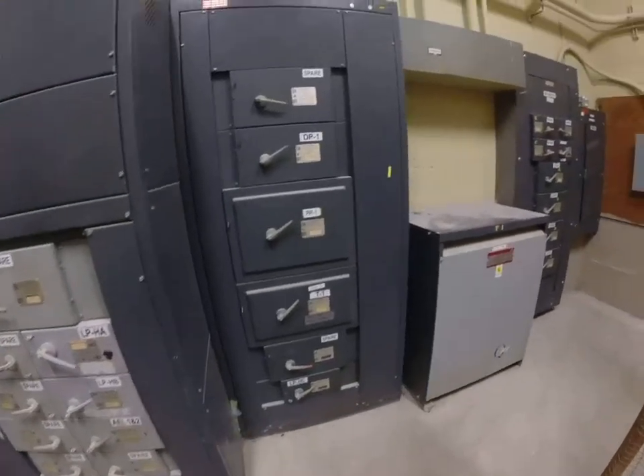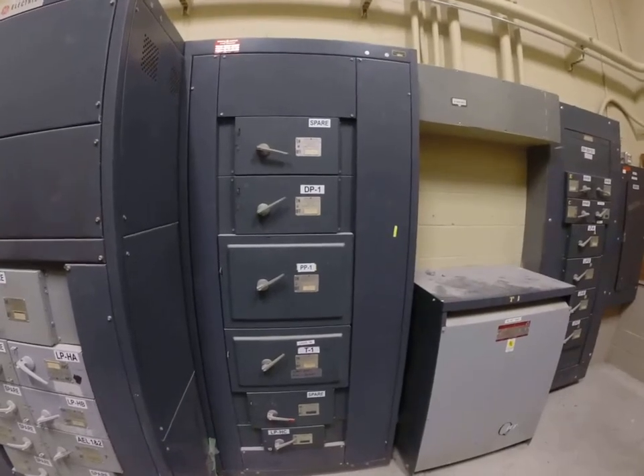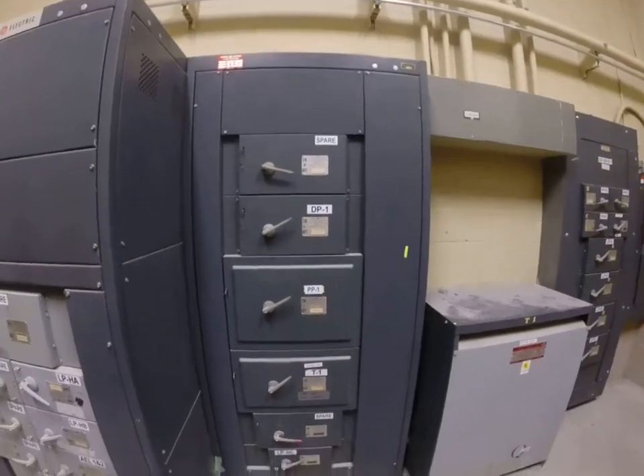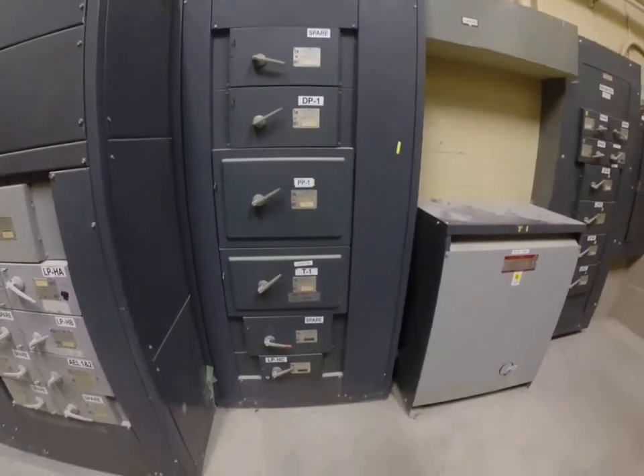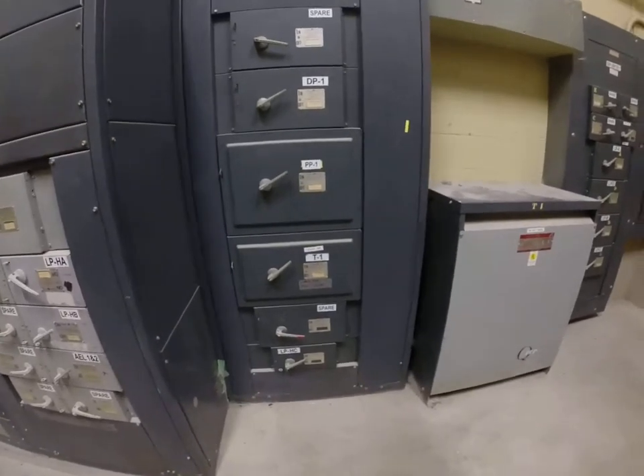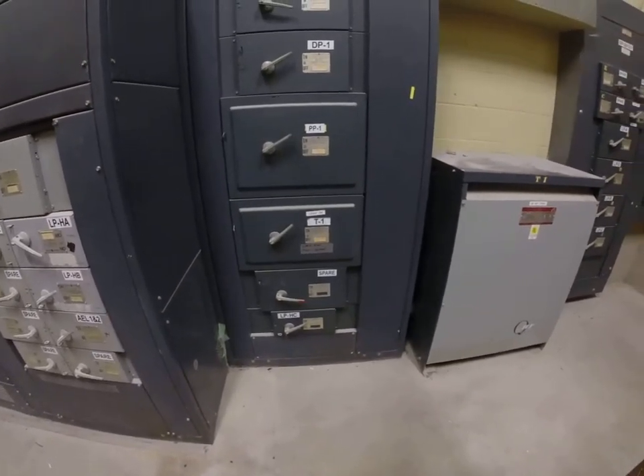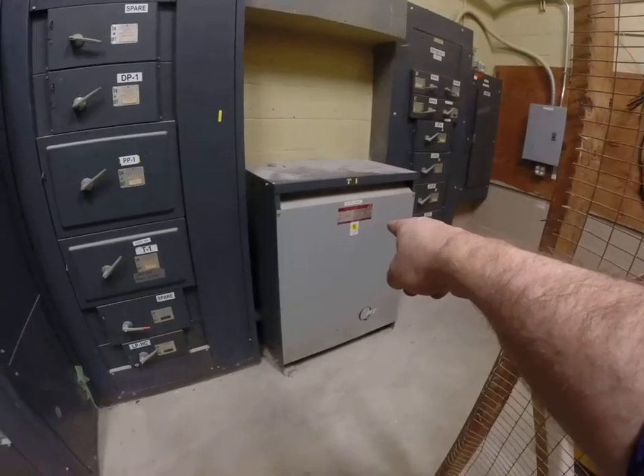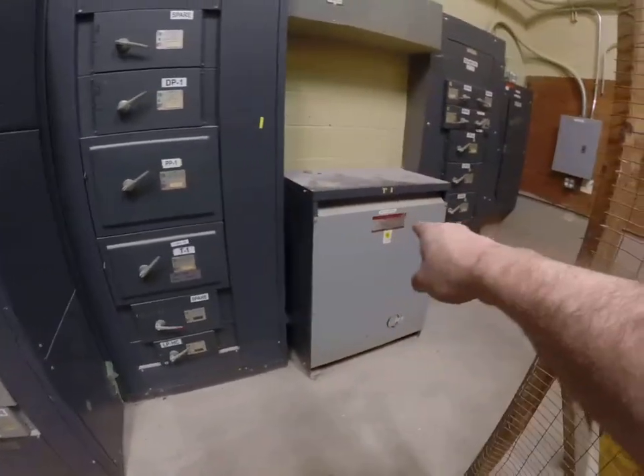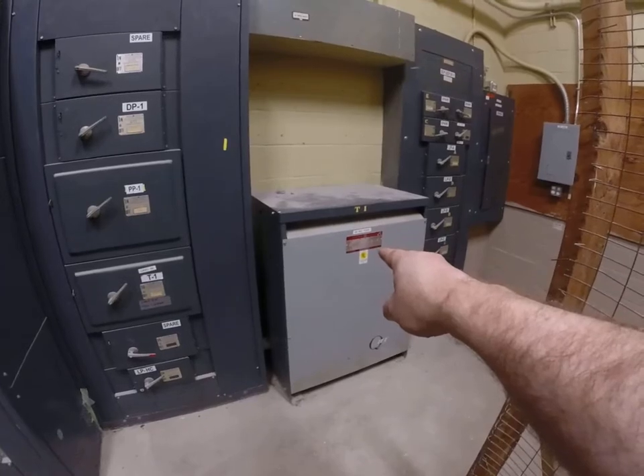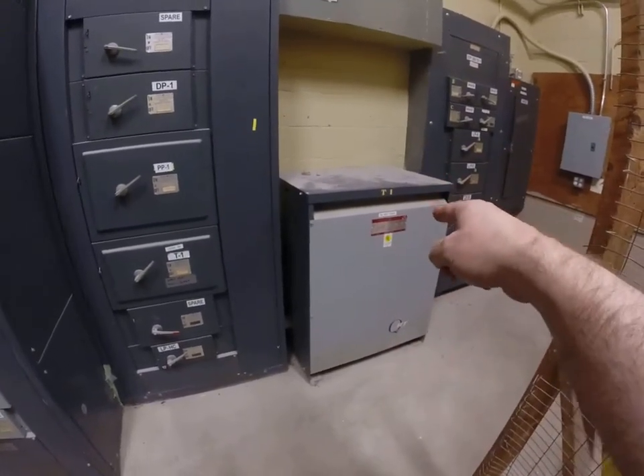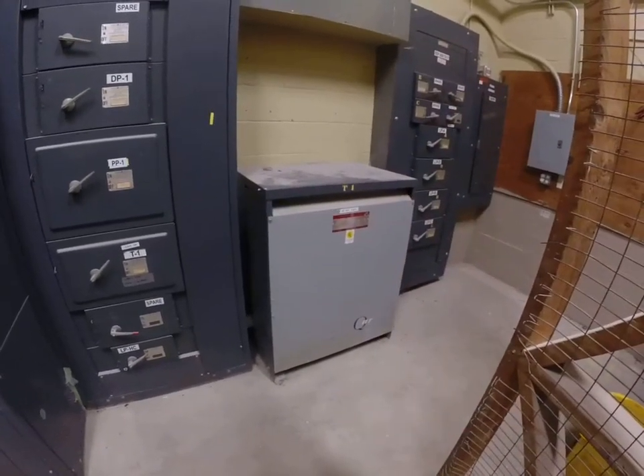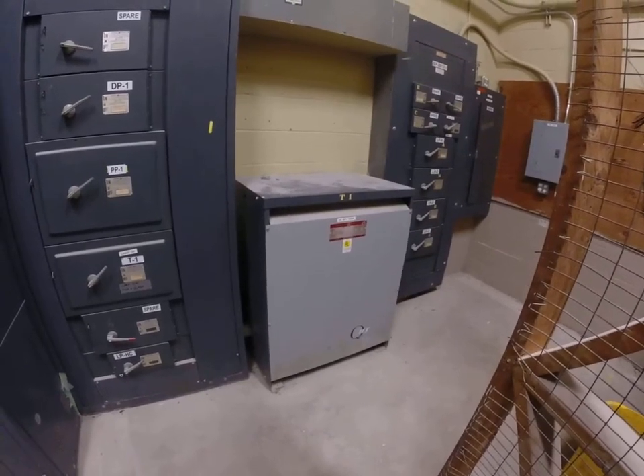We come over here, we've got another section of this. Spare breaker, DP1, PP1, probably stands for power panel 1, T1, likely the transformer over here. We've got 480 volts that's probably feeding the primary side of this transformer. That transformer is stepping our voltage down to 3-phase 4-wire 208/120.